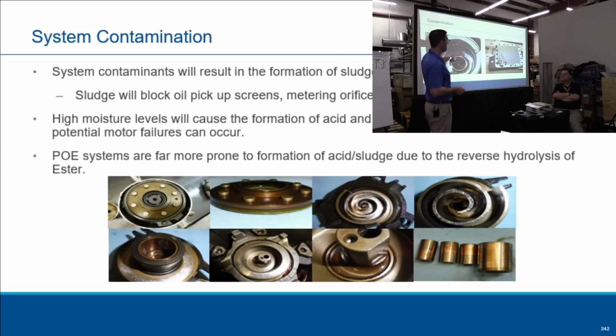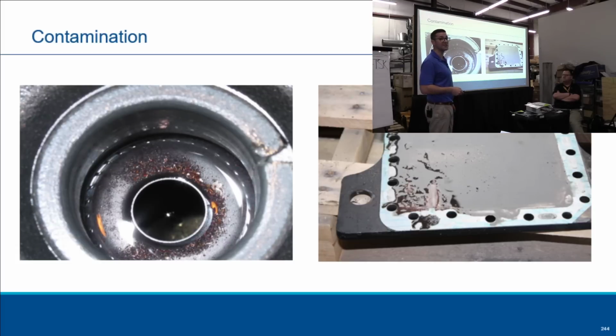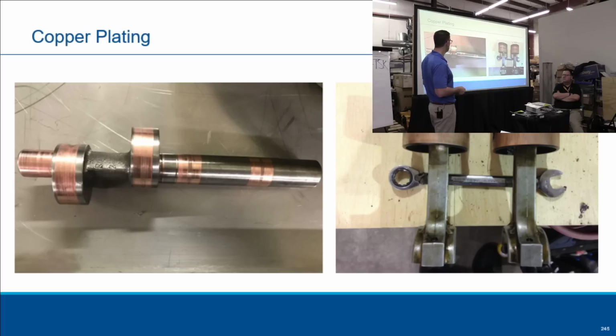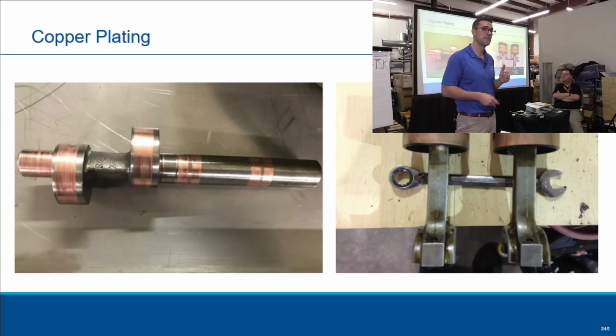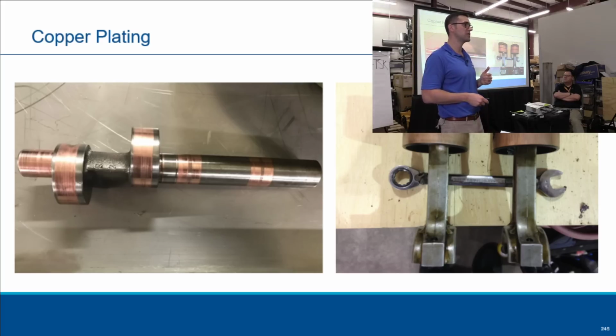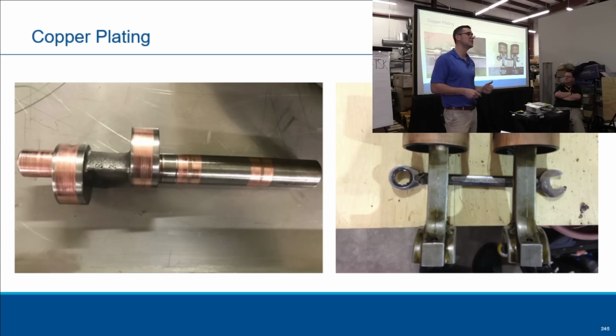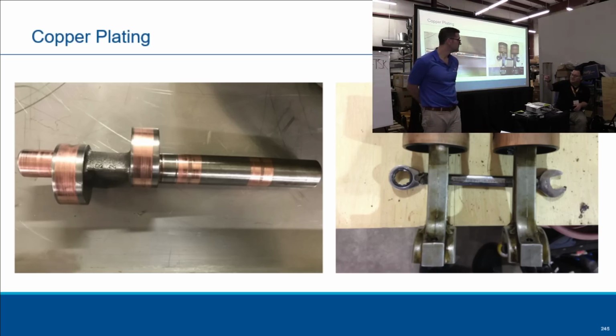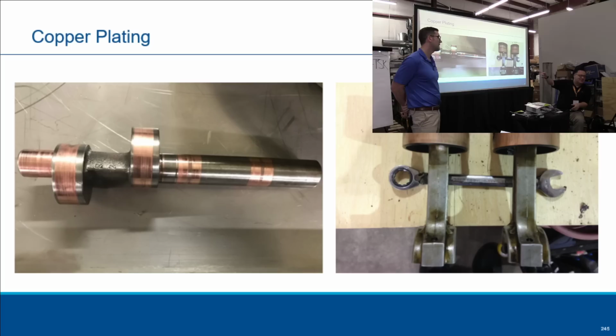You know, lots of dirt in systems. I work on lots of supermarkets, and there's definitely times that I've pulled compressors apart and they were pretty gross inside. But copper plating right here. Make sure, what do you need to evacuate a system down to? As low as you can. So 250. If you can get it down to 250, perfect. And it doesn't rise up. That was actually a teardown class I did. And Trevor saw the picture and he said, "Can you send that to me?" And one of the students actually took that as a souvenir when they left. But that's copper plating.